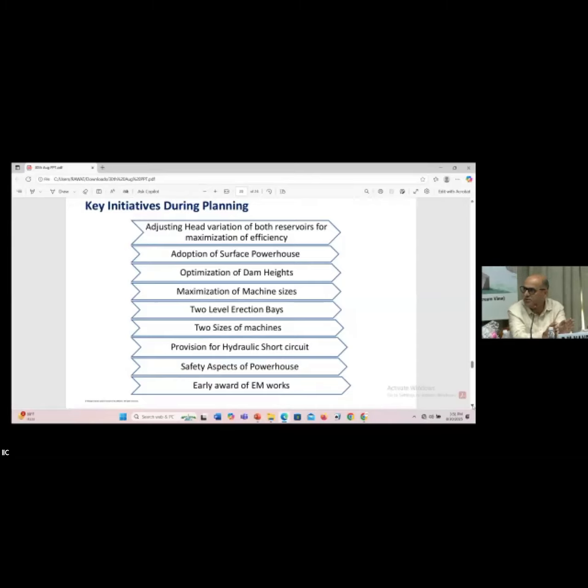Then the surface powerhouse - there's a lot of debate on surface versus underground powerhouses, but we opted for surface house because that squeezed the construction period by almost 12 to 14 months. Dam heights were optimized to make them easily and affordably executable. Machine sizes were maximized - we rarely see a 120-meter head with 240 megawatt machines, so we optimized the machine sizes to make the project very compact and effective.